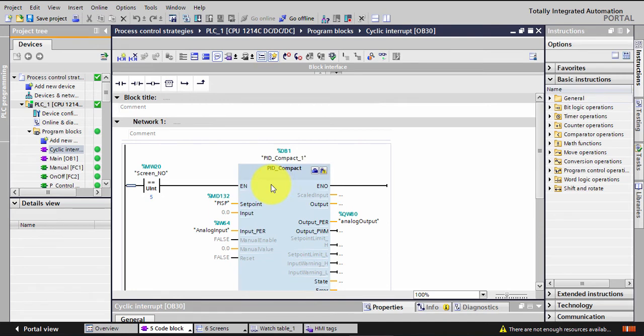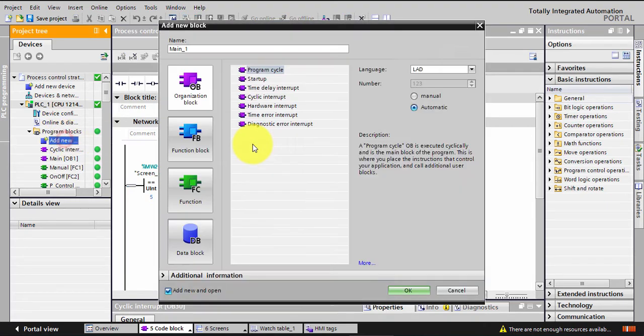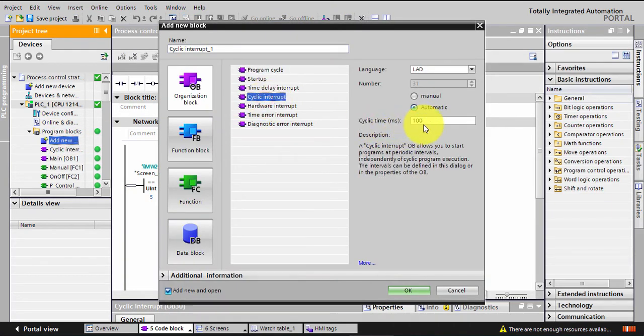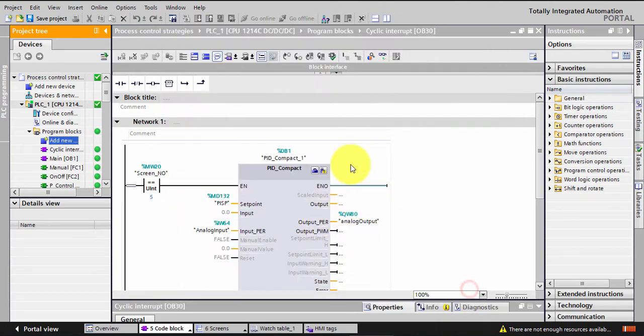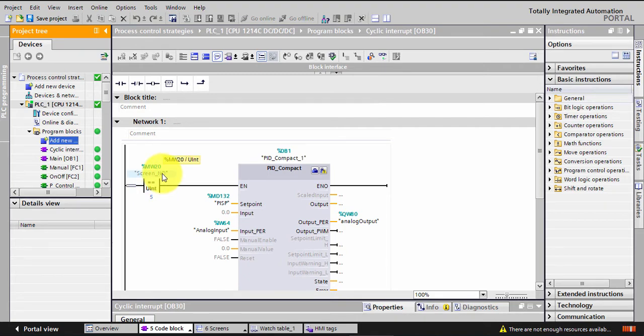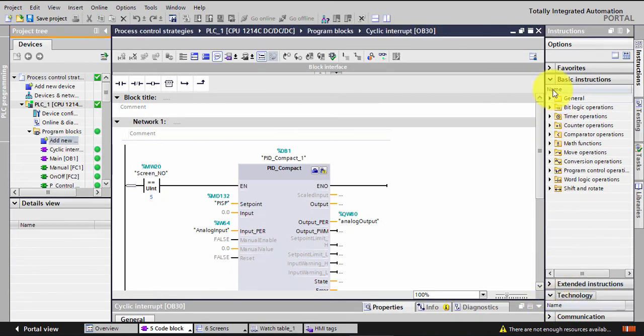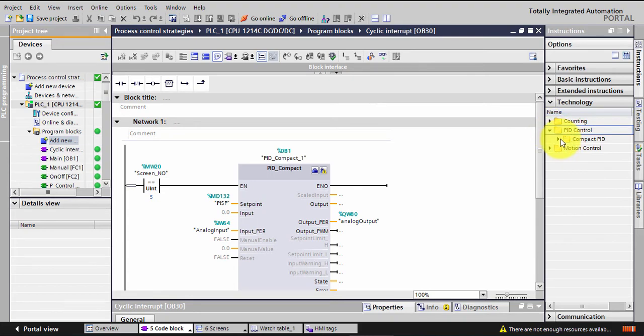A cyclic interrupt means whatever code is inside this routine will be executed every 100 milliseconds. So every 100 milliseconds, whatever you have inside will be implemented. I put a comparison so that if I'm pressing the PID or PI button in the HMI and the screen number is 5, this will be true. To add the PID Compact, you go to Technologies, then PID Control, and use PID Compact.